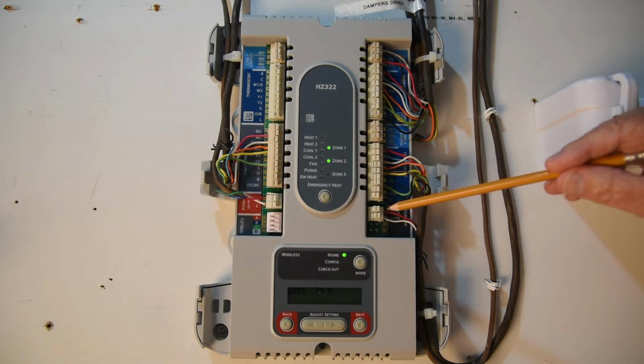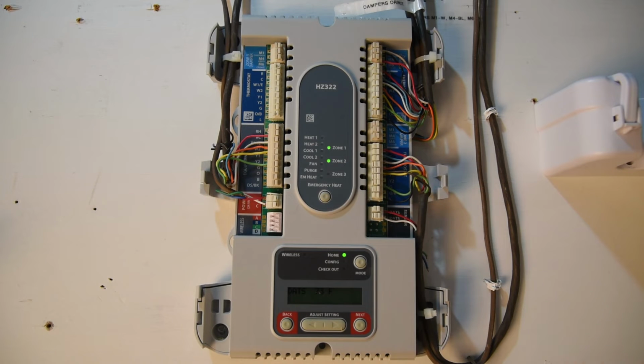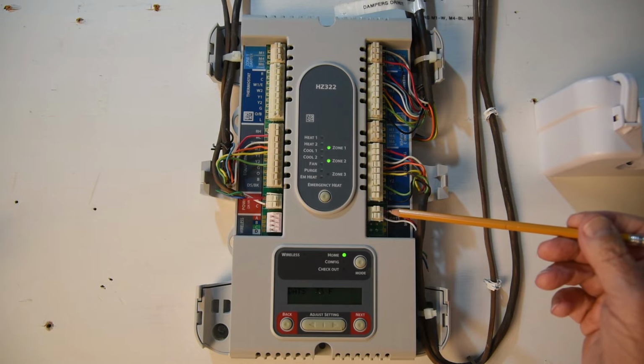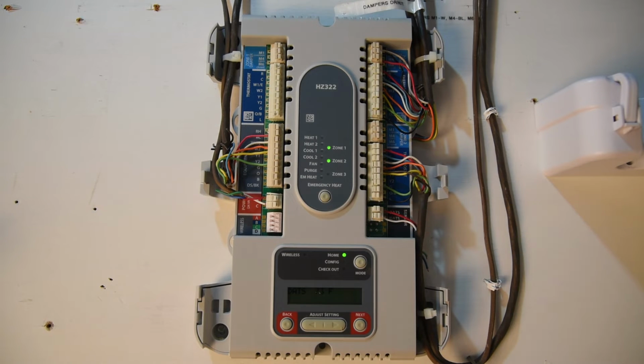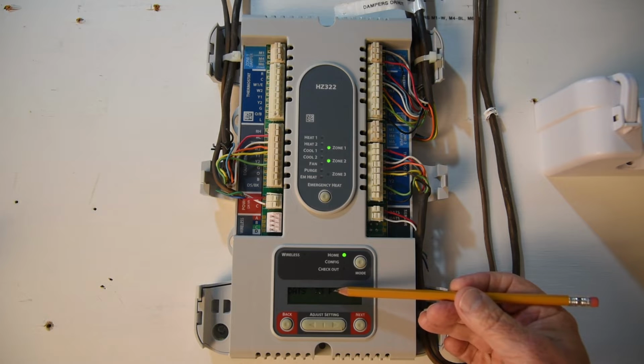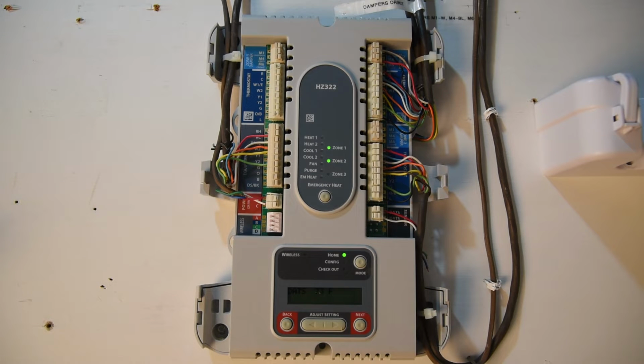The temperature sensor here, you have 2 wires on the temperature sensor. It doesn't matter which order they're in. It just measures resistance and converts that into a temperature. Right now, this is showing 73 degrees in the duct. That duct sensor should be put in the duct about 3 feet from the top of the air conditioning coil.